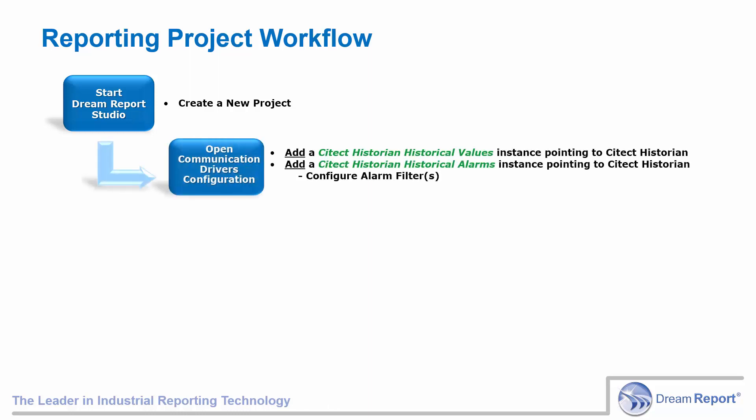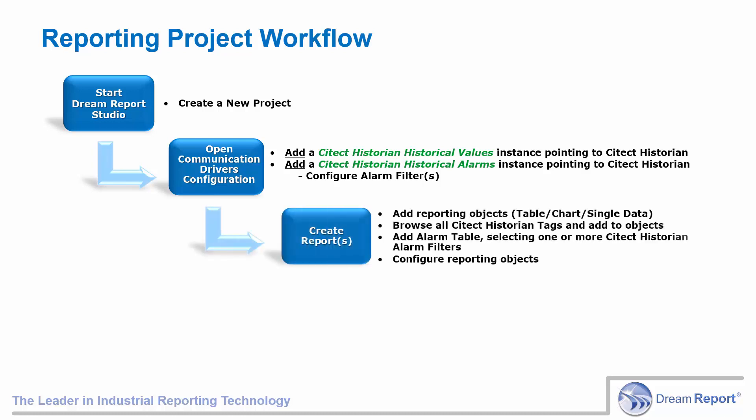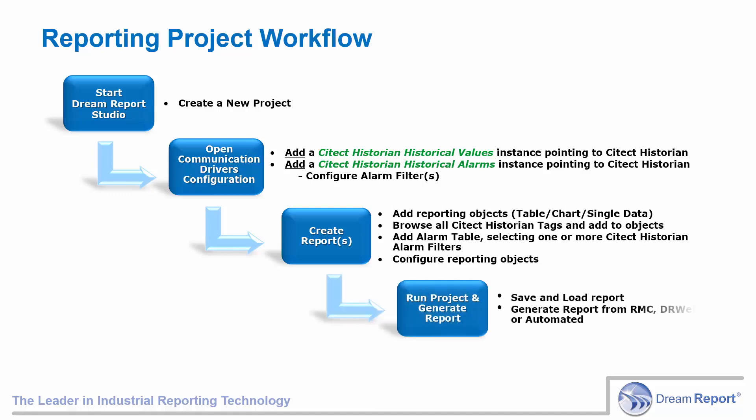In this final slide, we'll follow a typical workflow in creating a DreamReport project using data logged in the Citect Historian. First, we'll open DreamReport Design Studio and create a new project. Then we'll open the Citect Communication Drivers folder and add and configure an instance of the historical values driver to our Historian. We can add additional instances to other Citect Historians as well. We'll also add and configure an instance of the historical alarms driver to our Historian. At this point, we're ready to create a new report. We can drop any kind of tabular, chart, or calculation object on the report and browse the Historian for any tags to use on the object. After configuring the object, we can start DreamReport's runtime engine and generate the reports.